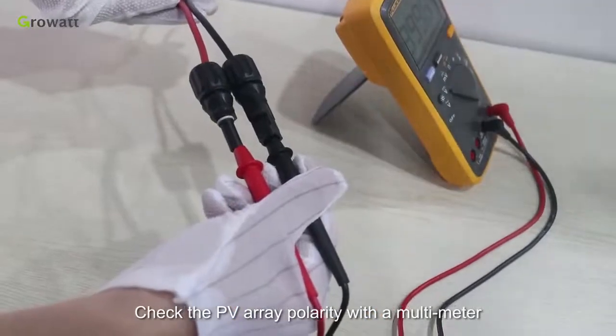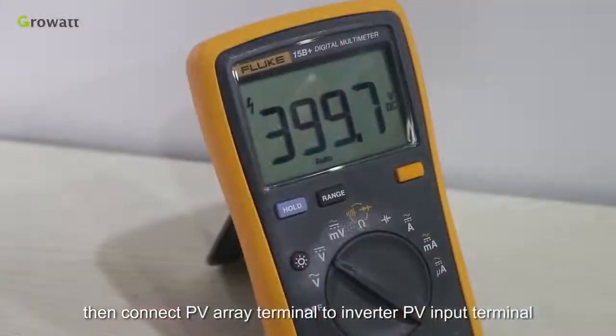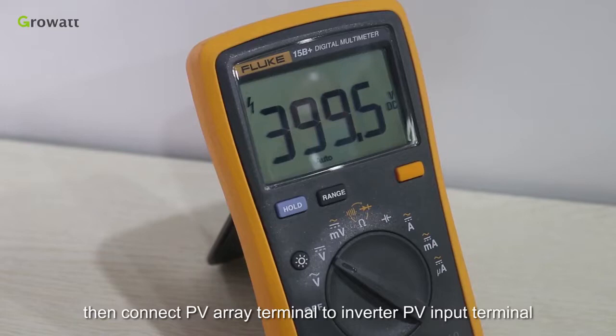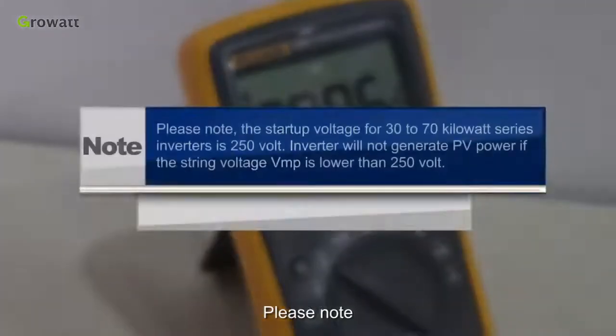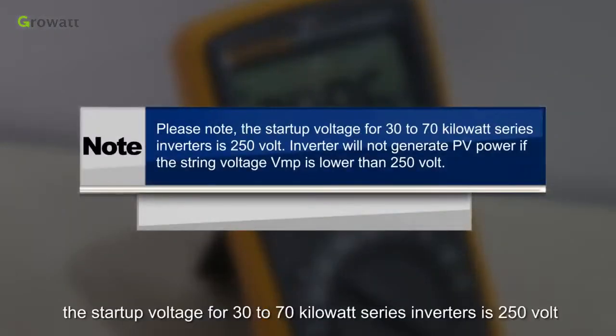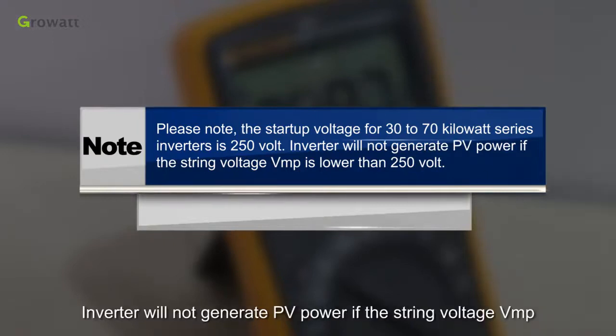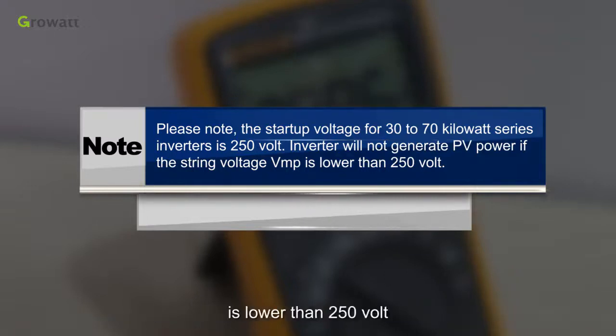Check the PV array polarity with a multimeter. Then connect the PV array terminal to the inverter PV input terminal. Please note, the startup voltage for 30 to 70 kW series inverters is 250 volts. The inverter will not generate PV power if the string voltage is lower than 250 volts.